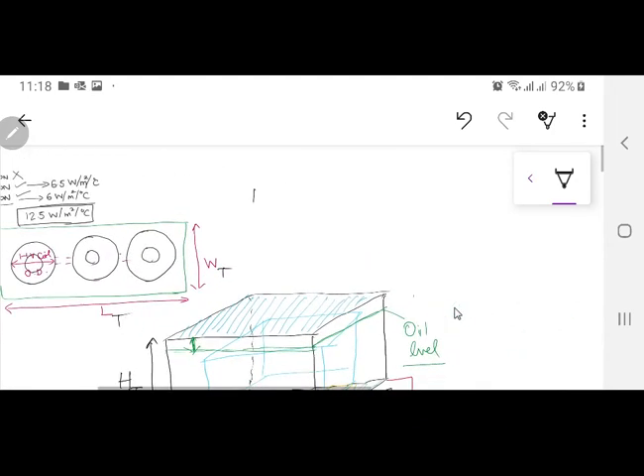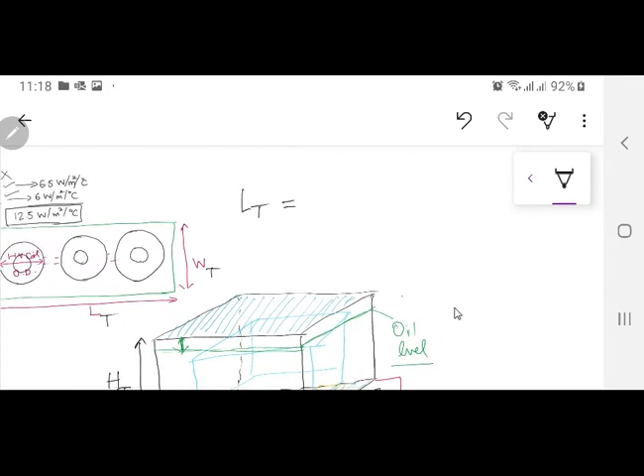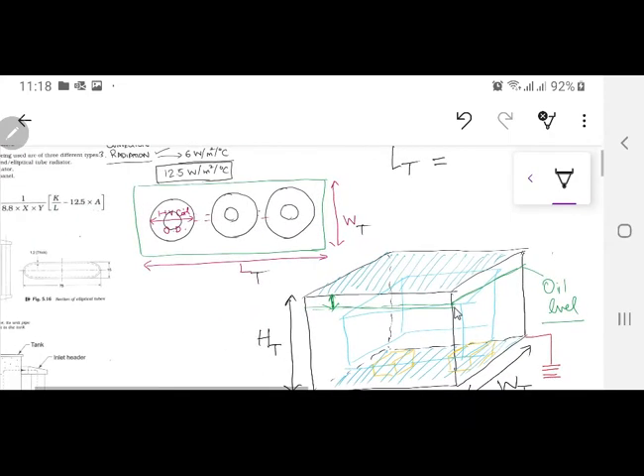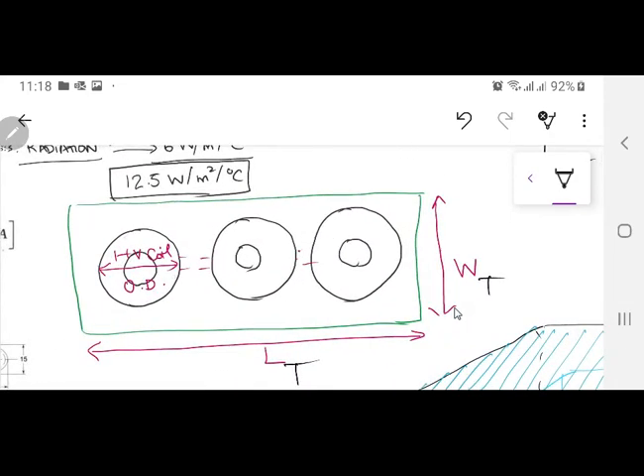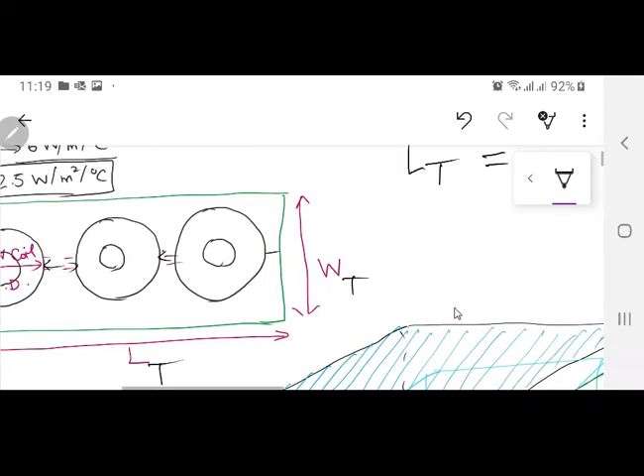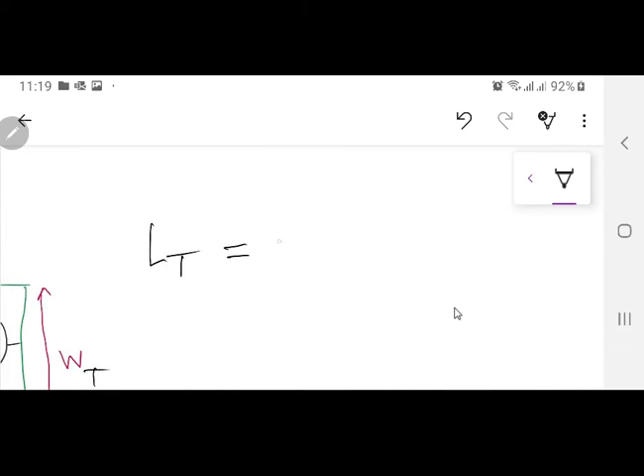Now what is this LT? According to this book, what will LT be equal to? Length has to be equal to the high voltage coil diameter, 3 of them, then this distance and some clearances. So the LT formula can be written as 2 times the core limb (CL) of the transformer core.